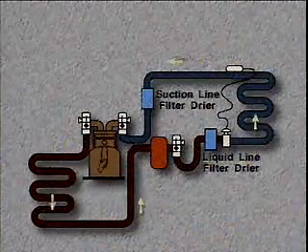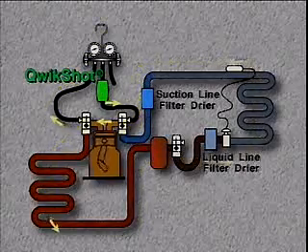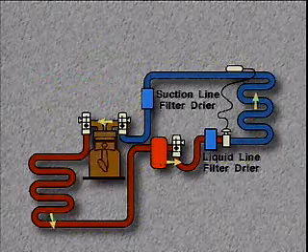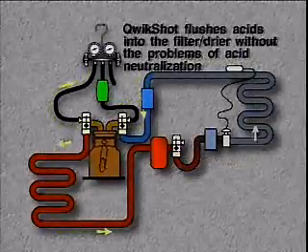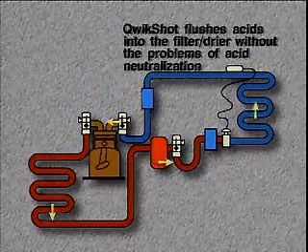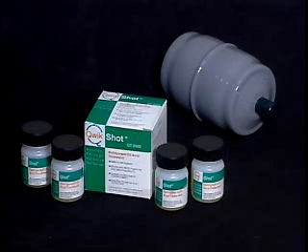QwikShot does not neutralize the acid — rather, it flushes the acid from the oil and hard surfaces and allows the acid to be carried to the filter dryer, where it is removed, leaving no residue. QwikShot flushes the acids into the filter dryer, and because it does not neutralize the acid, it can be used with all oils and refrigerants. QwikShot never leaves any residue.